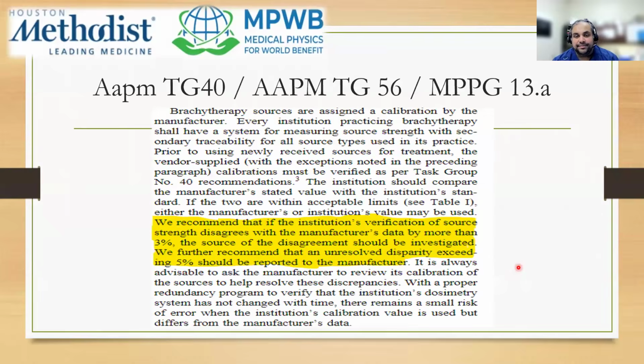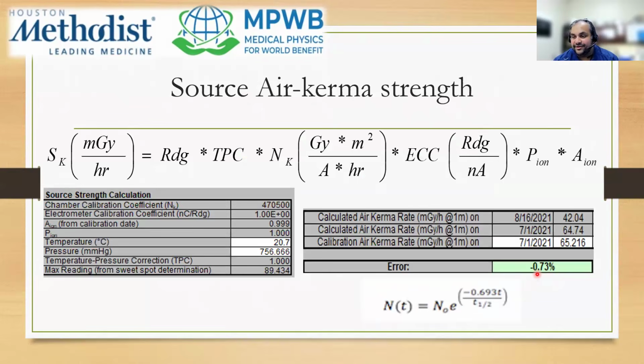As per the AAPM guidelines, if it's between 3 and 5%, you should at least investigate. Maybe there might be some sort of user error or setup error. But if it's more than 5%, after going through your several checks and possibly even asking your neighboring clinic if they have a calibrated well chamber, if you're sure that your readings are still more than 5%, that's when you have to report to the manufacturer. But ideally, you want this percent difference to be less than 3%.